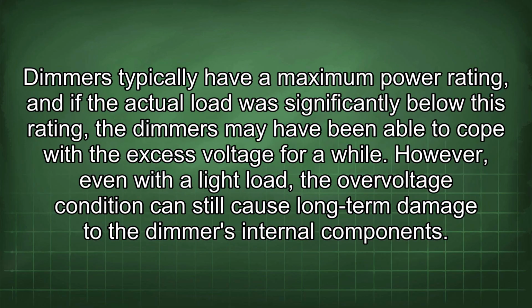Dimmers typically have a maximum power rating, and if the actual load was significantly below this rating, the dimmers may have been able to cope with the excess voltage for a while. However, even with a light load, the overvoltage condition can still cause long-term damage to the dimmer's internal components.